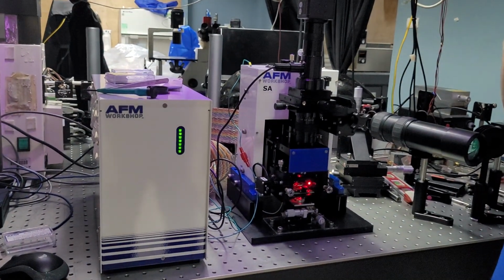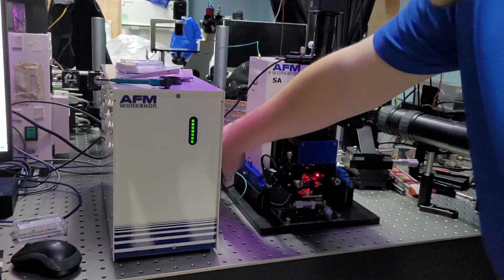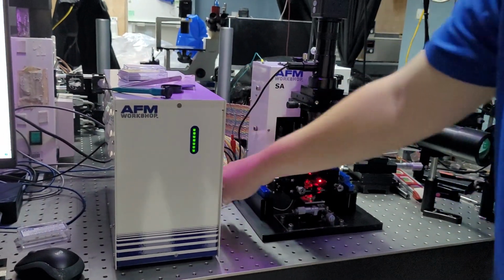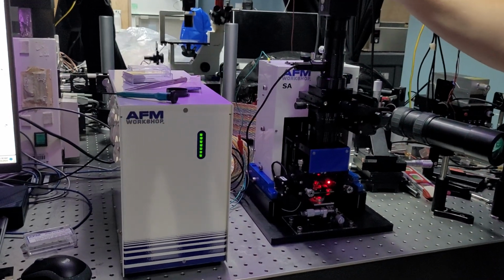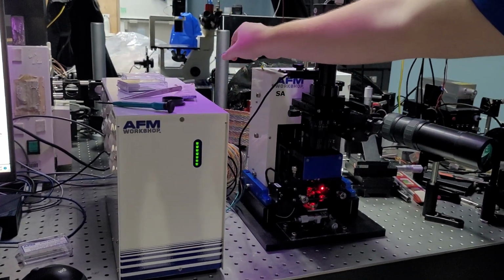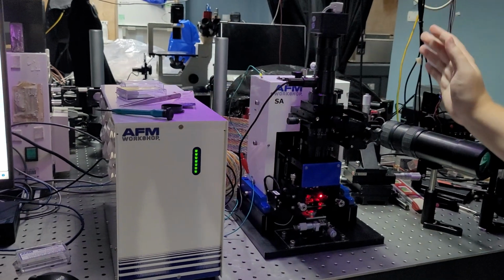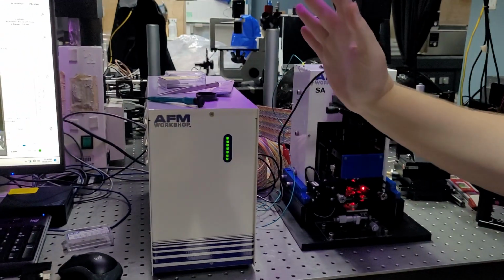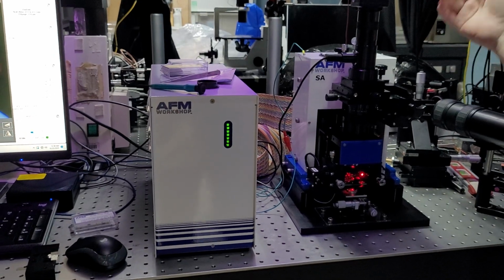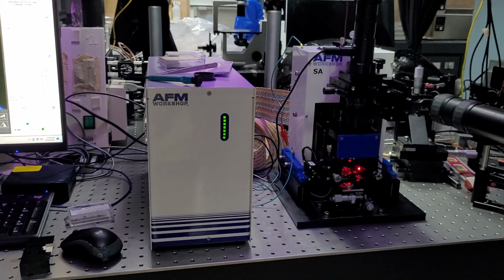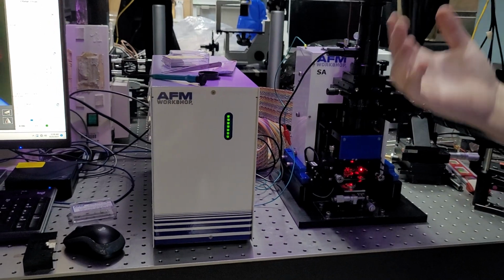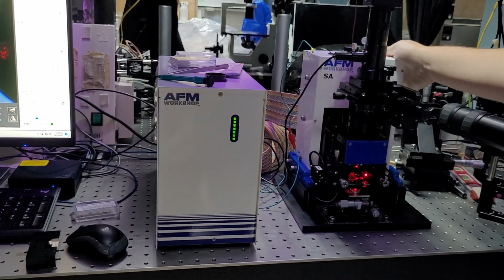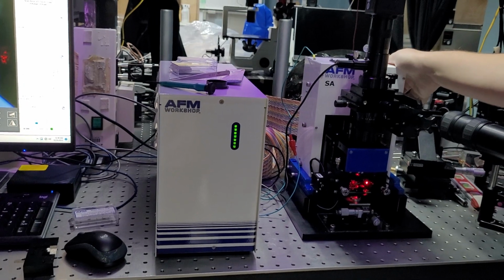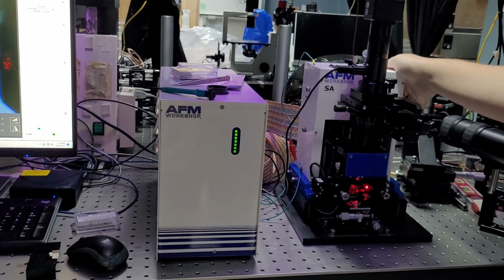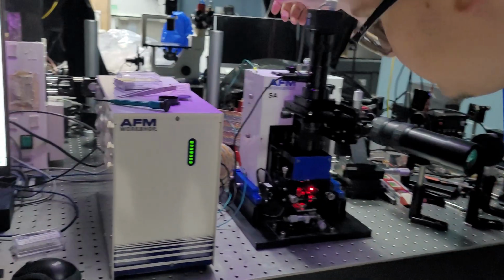Should be everything about the AFM. As far as cables, like I said, there's a variety of cables. There's a USB here, there's a light cable here, there's a grounding wire here that allows any potential charge that builds up to dissipate through the system. At the back there is a 60-pin ribbon cable. I'm just going to go ahead and say this. In the future, if and when you move the AFM, please make sure that the 60-pin ribbon cable is fully plugged in.